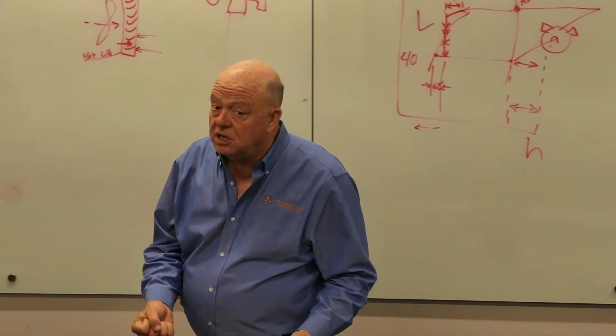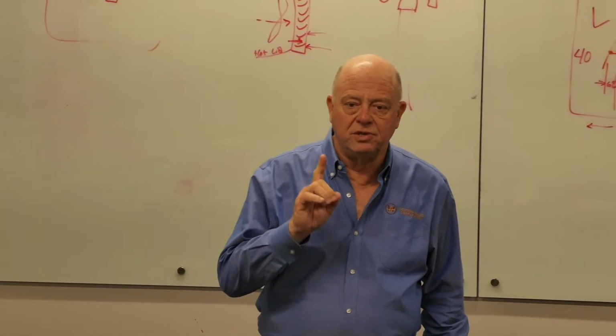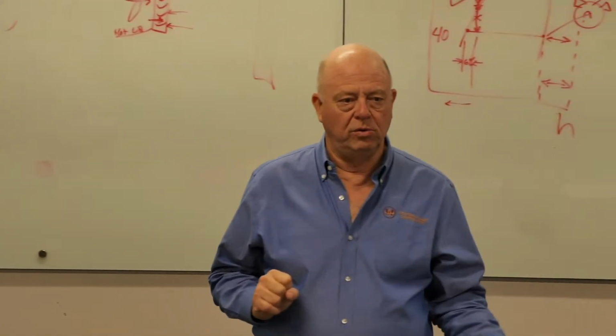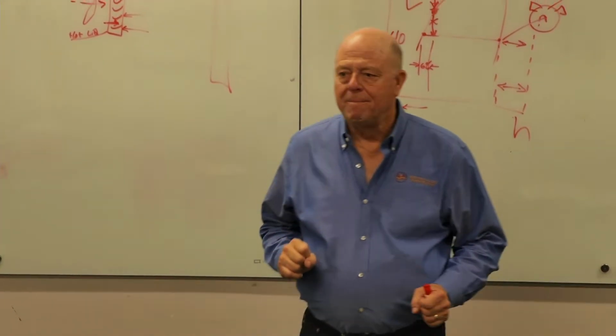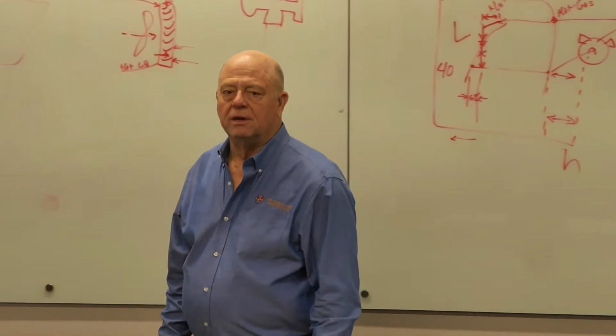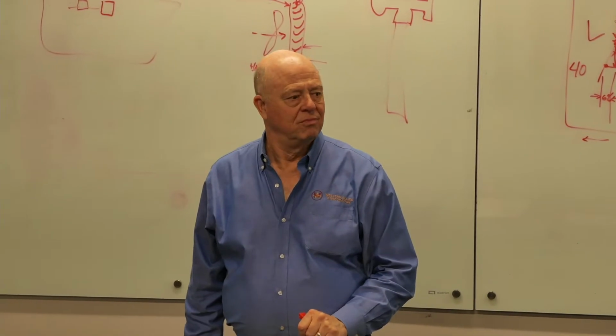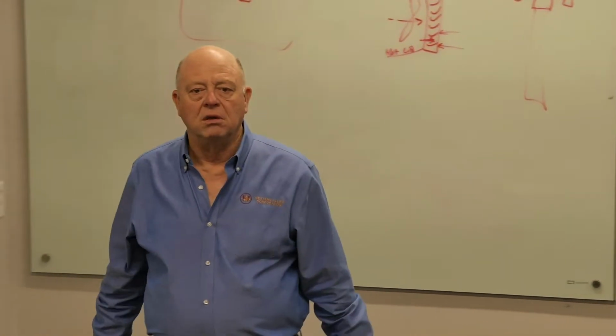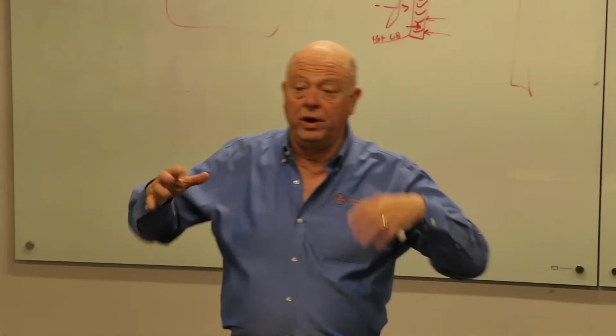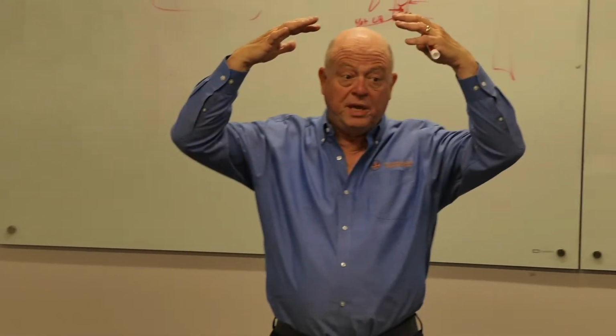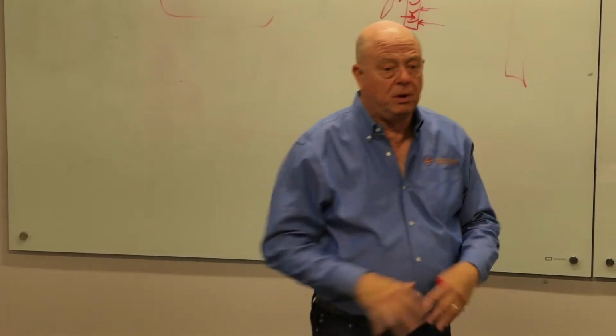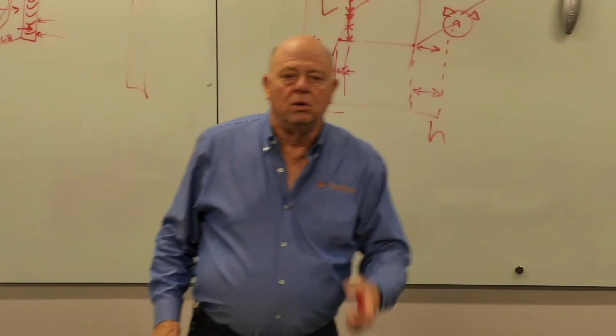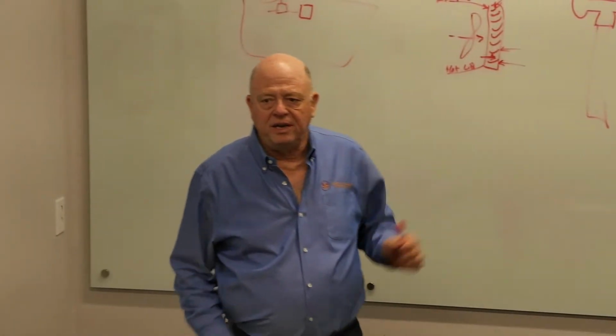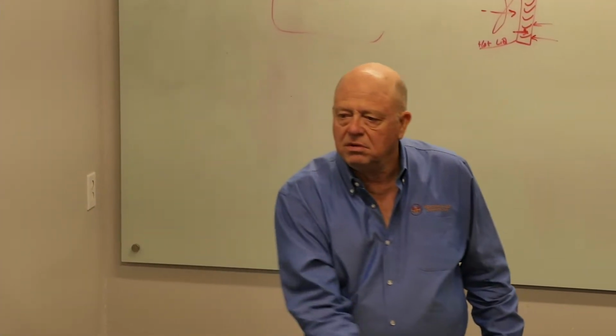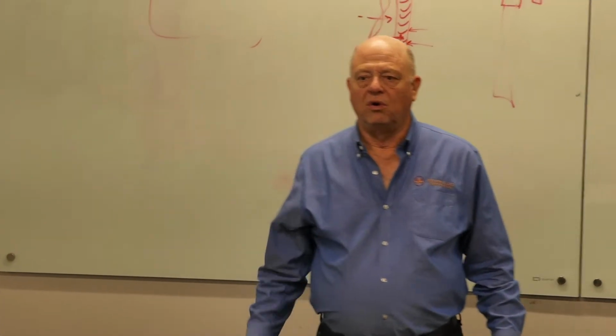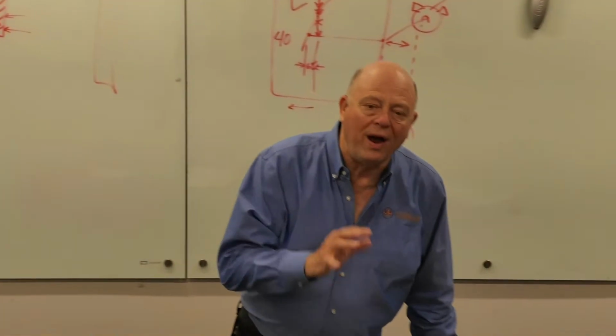But it worked for quite a while. It was only because of the leaks that we ended up getting them out of there. And that's because there is an exception here to why you don't bury a refrigerant line. This is their satellite uplink facility. It's 24/7. It never cycled off very long. Depending upon whenever the peak broadcast times were, they would have peak loads. The load did vary somewhat, but it was never zero. And so you very seldom had any length of time for the gas to condense or for the liquid to overly subcool. And that's why it lasted as long as it did.